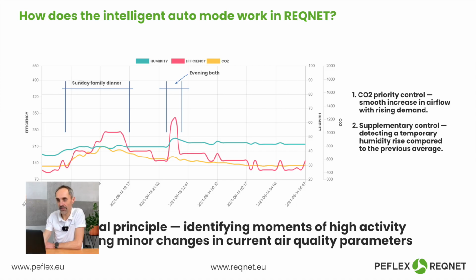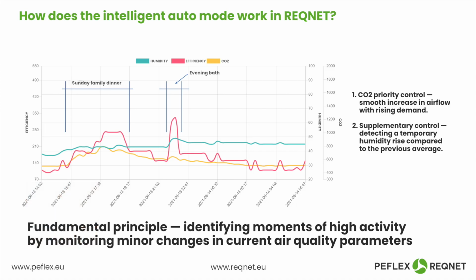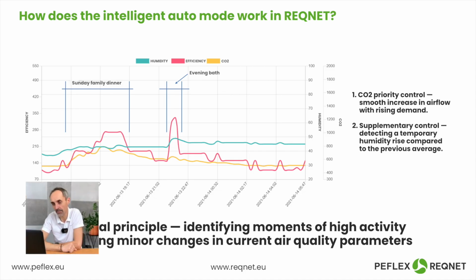How does the smart mode work in REQNET ventilation units? So, the device monitors air quality, specifically the concentration of carbon dioxide. That means as the concentration increases, the device's output also increases. We reach the maximum level. The device operates at that level for a while, and when the pollution starts to decrease, the unit also adjusts and lowers its output, meaning it reduces the amount of air flowing through. So that's how it works, based on the carbon dioxide sensor.